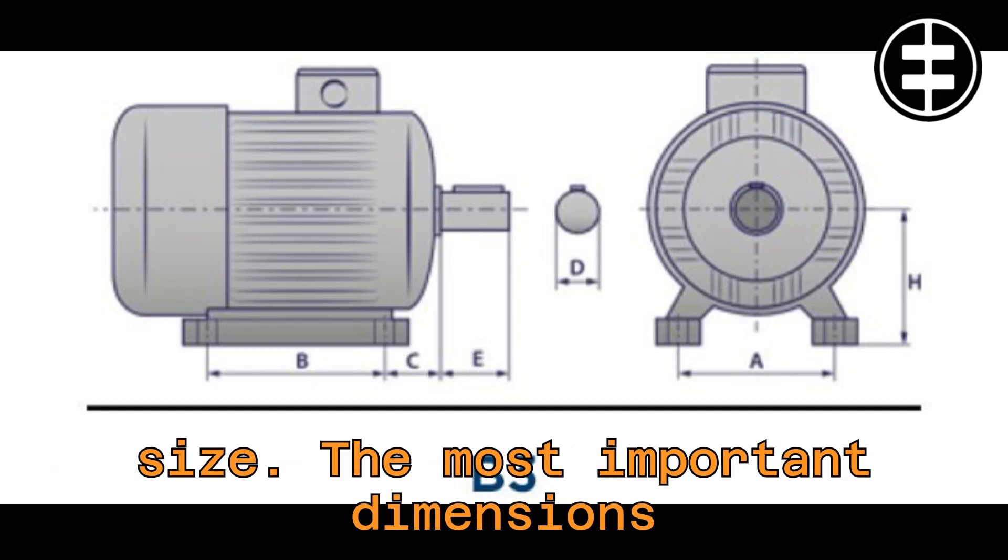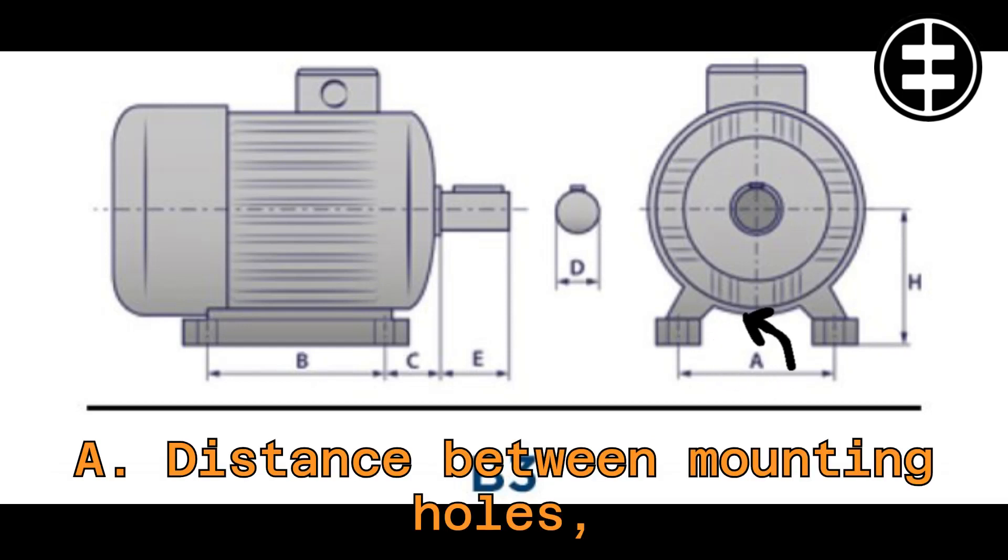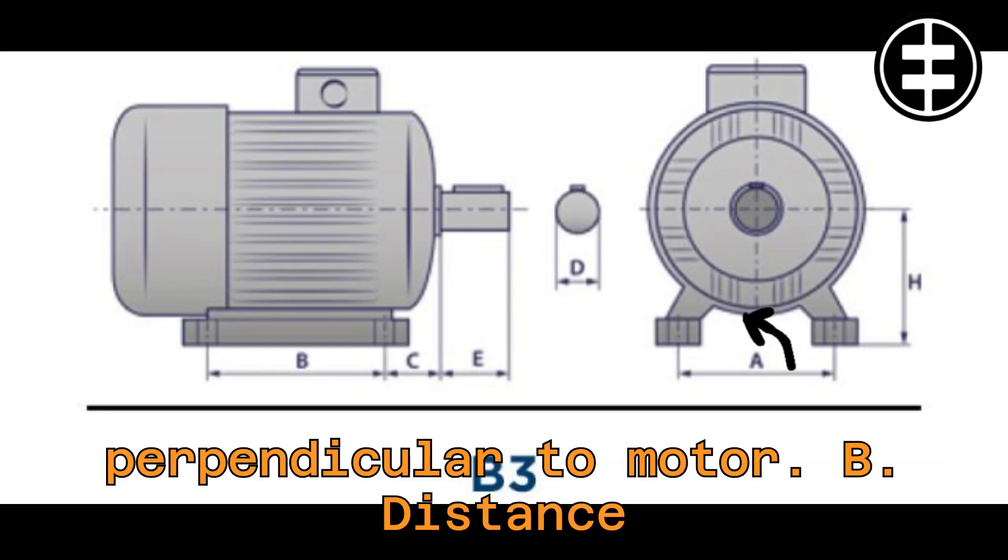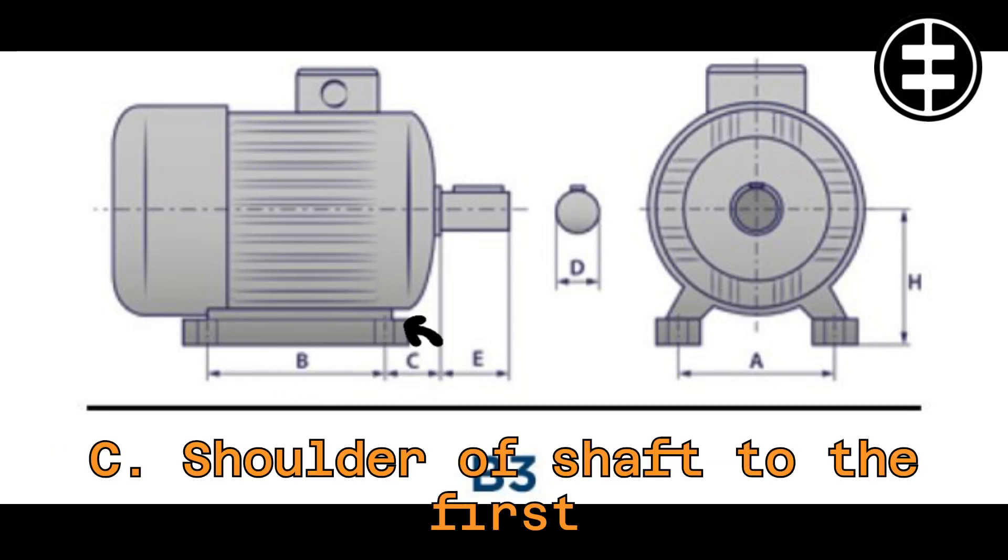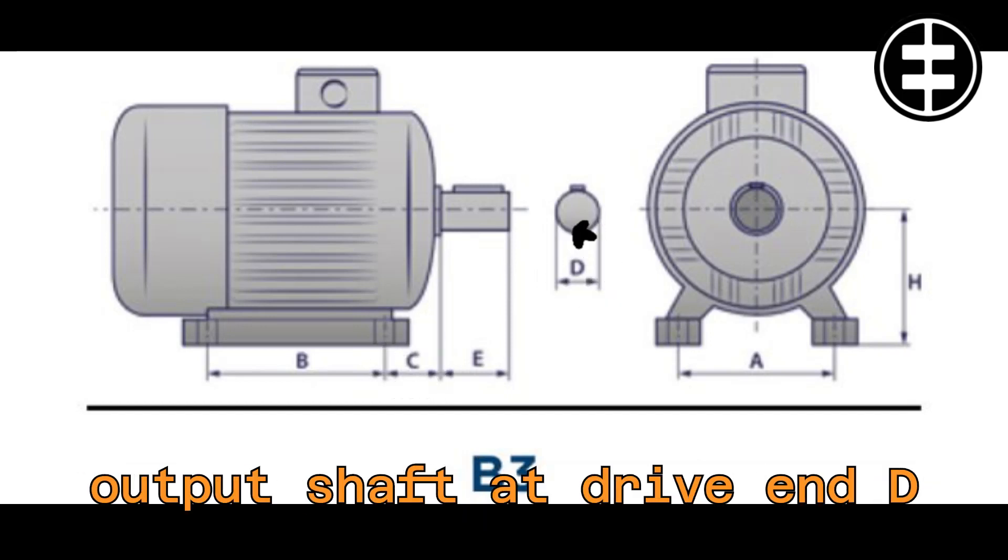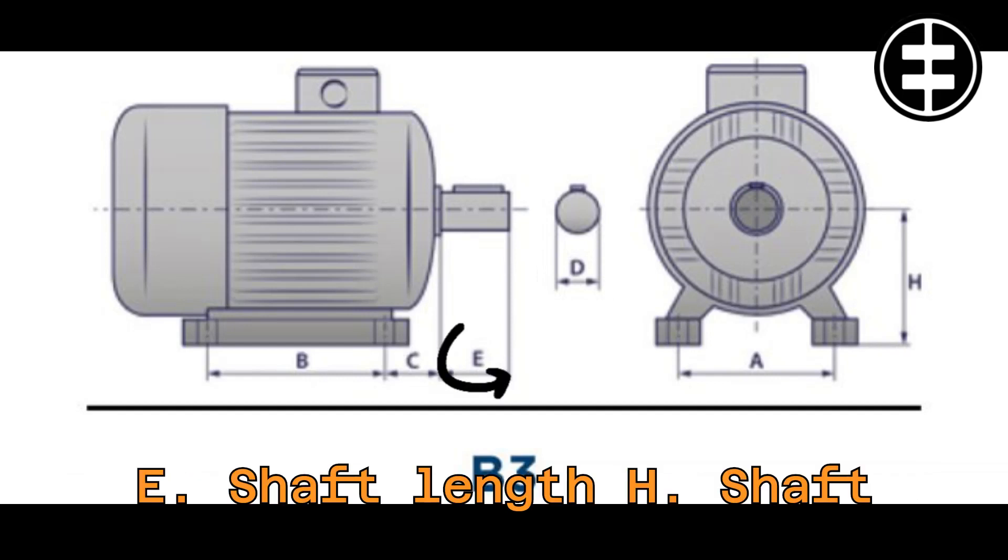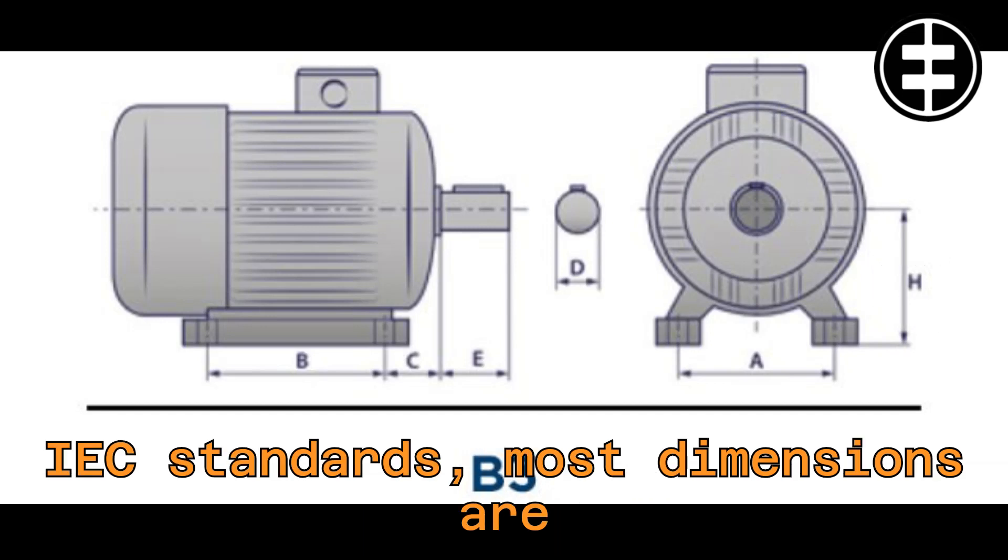The most important dimensions according to the IEC standard are: A. Distance between mounting holes perpendicular to motor. B. Distance between mounting holes parallel to motor. C. Shoulder of shaft to the first mounting hole. D. Diameter of output shaft at drive end. E. Shaft length. H. Shaft height.